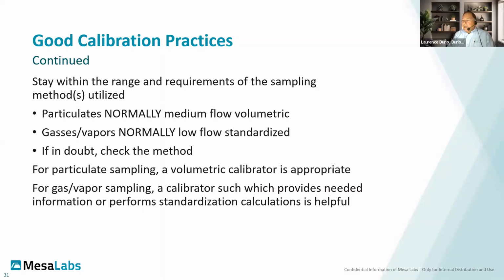If you're doing gas and vapor sampling, you can use a volumetric with a separate source to give you temperature and pressure. That's pretty awkward. There are pumps and calibrators available that give you readings of your absolute pressure and absolute temperature, or that will actually do the standardization calculation for you. If I was doing very occasional gas and vapor sampling, I might go with a volumetric to save a few dollars. If I was doing a lot of it, I would go with one that did the calculation, both to save the calculation time and to eliminate the human error of dividing where you're supposed to multiply or vice versa.